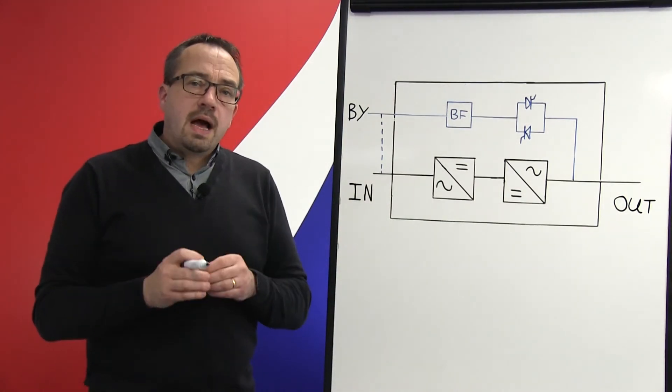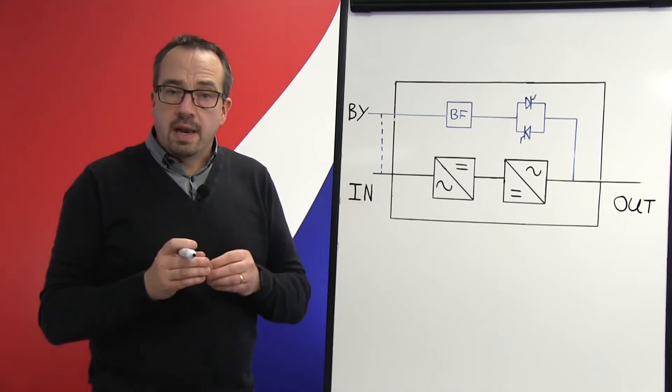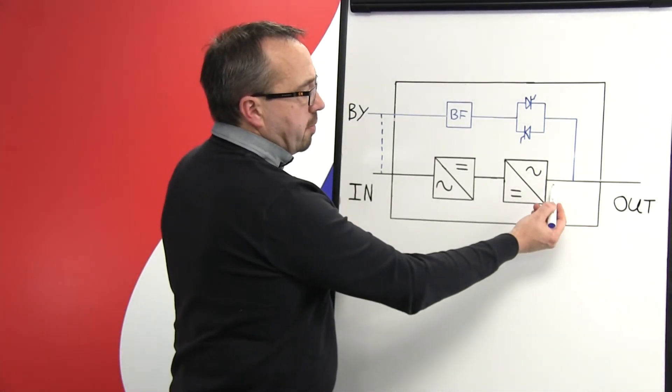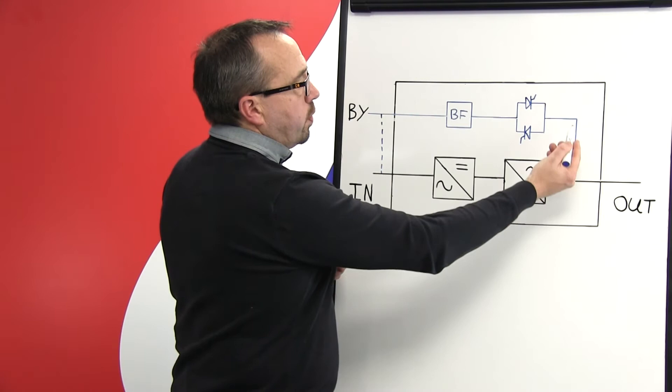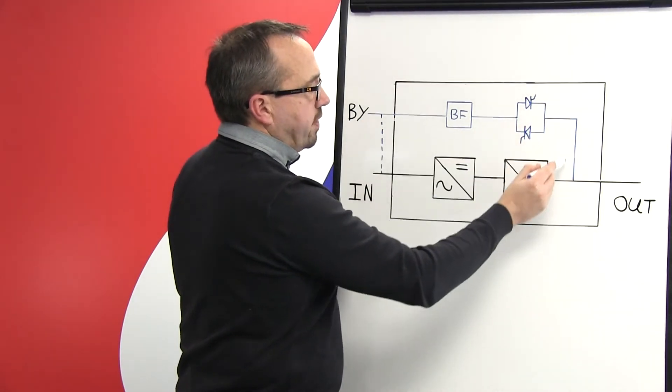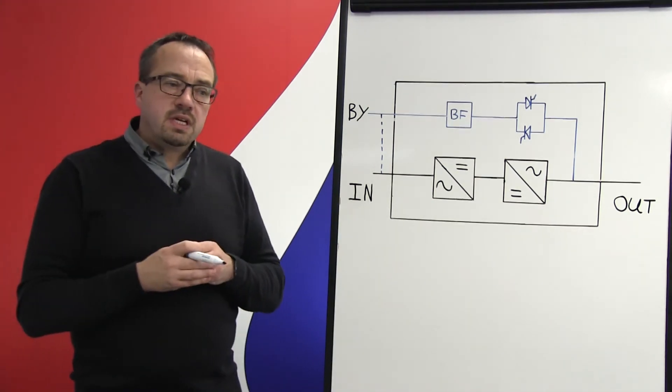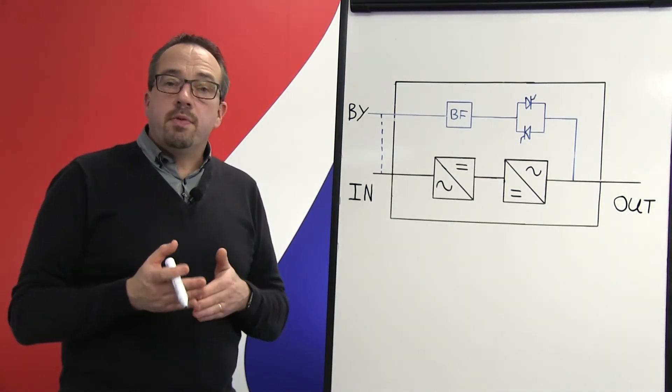One of the main things that must happen within any UPS system to allow a zero break transfer is that the output voltage waveform from our inverter must always be in synchronization with the supply voltage waveform coming in via our bypass switch. If that's not in sync, the UPS can never make a seamless transfer.